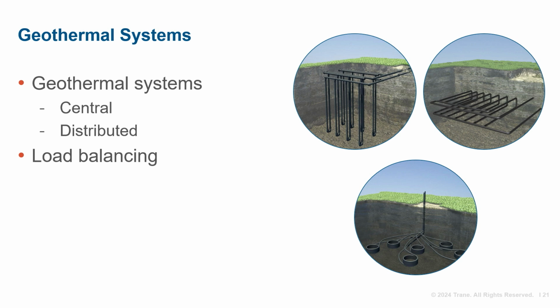Identifying the peak and annual heating and cooling loads is important. Peak loads to ensure the geothermal field is adequate to source or sink the load needed. This may be important to ensure that the earth temperature does not rise or fall over time due to an annually unbalanced load. If this were to occur, system operation efficiency is degraded. For example, in a cooling dominant building, more heat is rejected to the earth than extracted. Eventually, the earth warms, resulting in elevated return fluid temperature. Increased fluid temperatures at the condensers of heat pumps in the building, whether distributed or central, bring increased energy consumption. The cooling units must produce more lift.